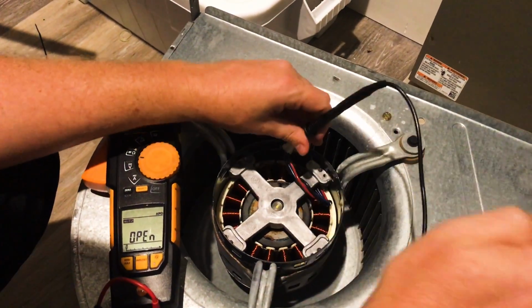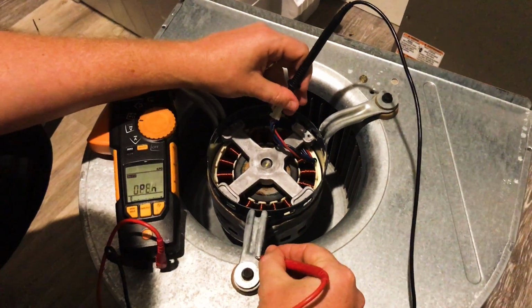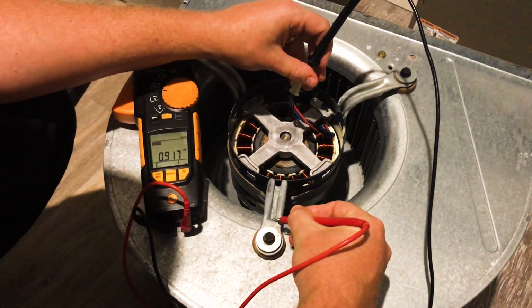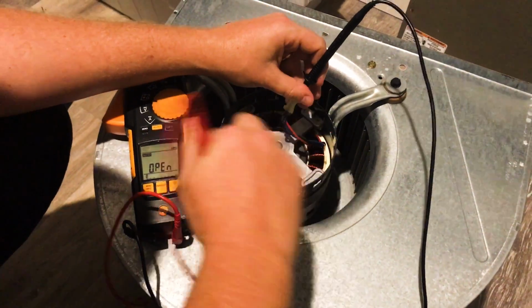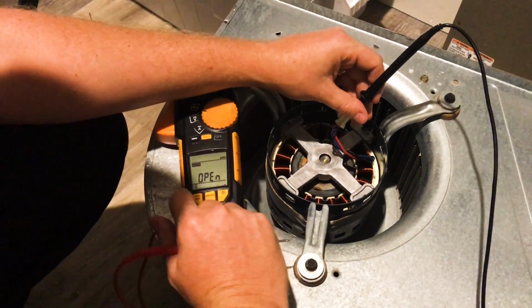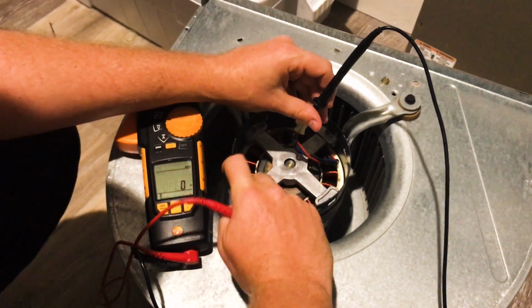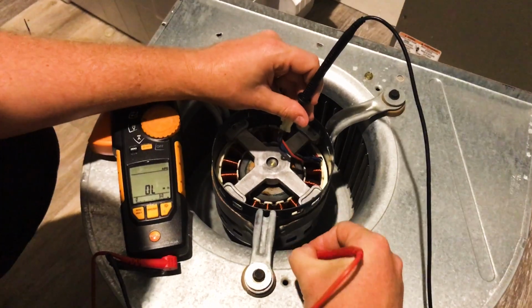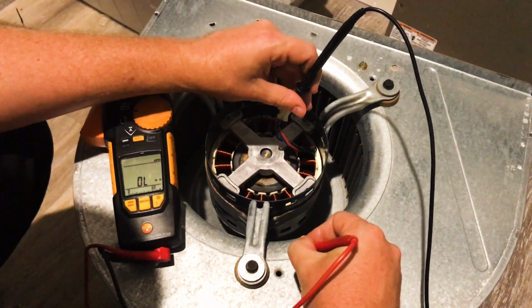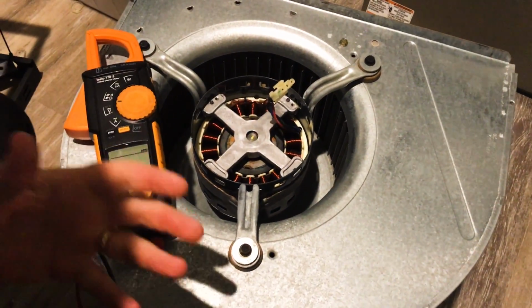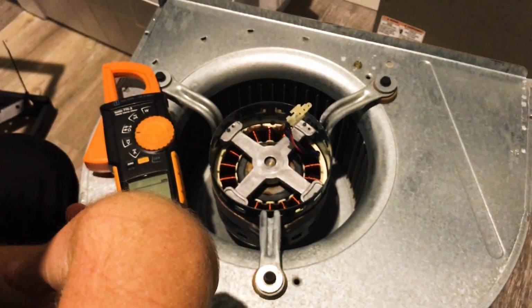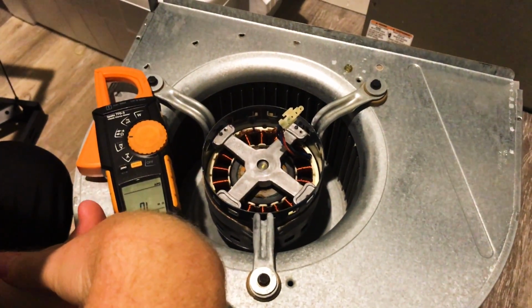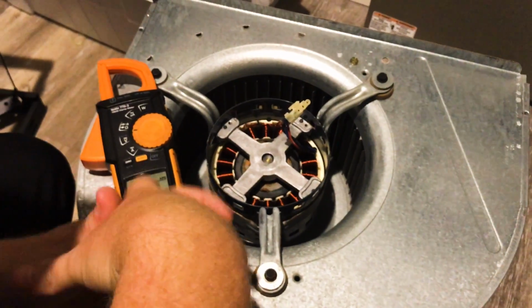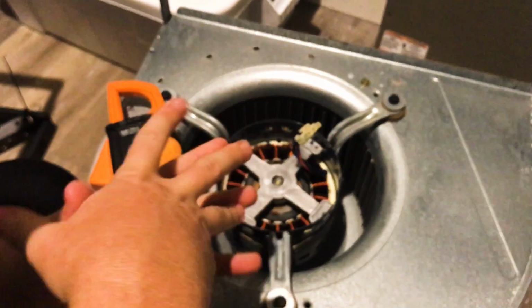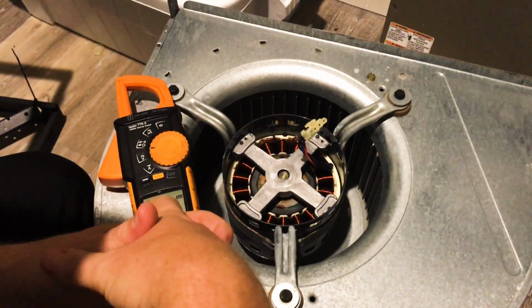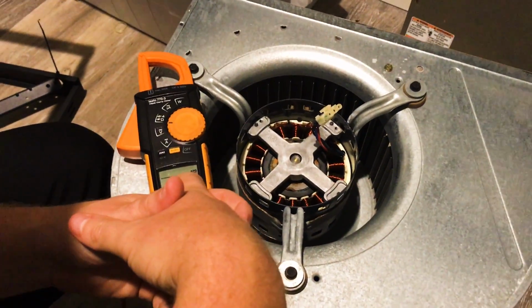All right, now we're going to check each winding to ground. Now again, that's not the issue that we're having with this unit, so I would be very surprised if we would find anything significant to ground. So it's reading in the nanofarad scale, but let's change it to just ohms. It's going to go to the mega ohm scale. We got nothing. So the motor spins well, shows no signs of overheating, shows no significant bearing play, and I'm not seeing any rotor damage, and the windings ohm out properly to each other and to ground. We have no path to ground, so I feel good about going ahead and installing our motor module.